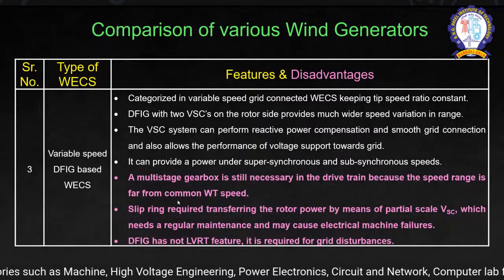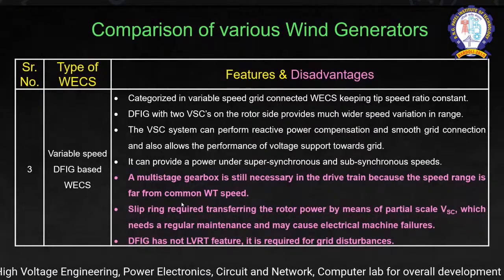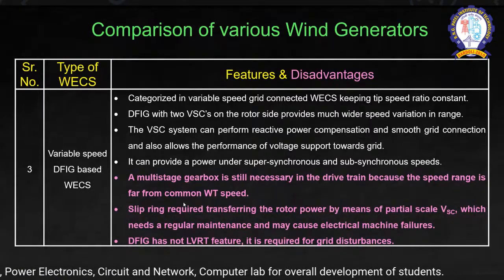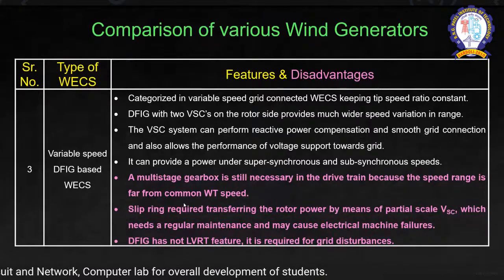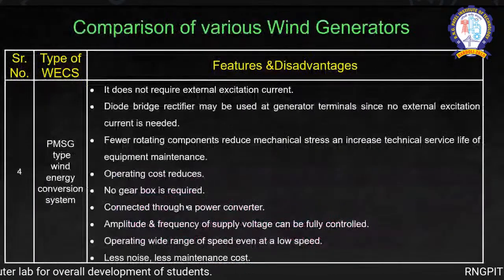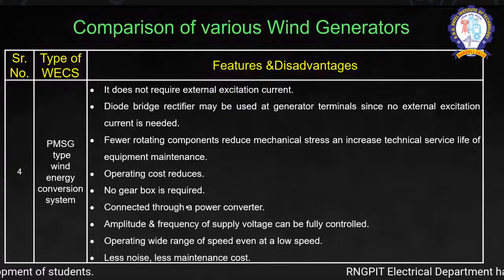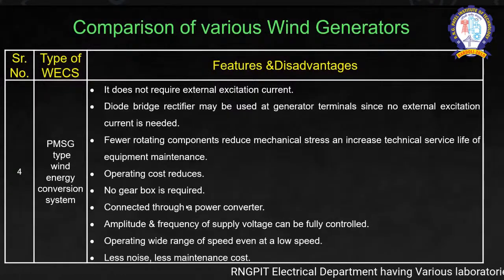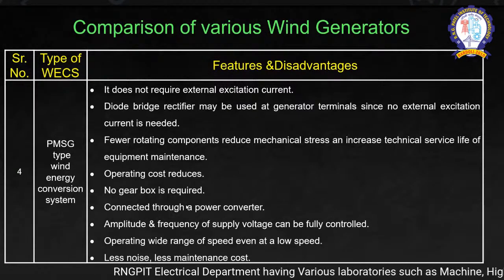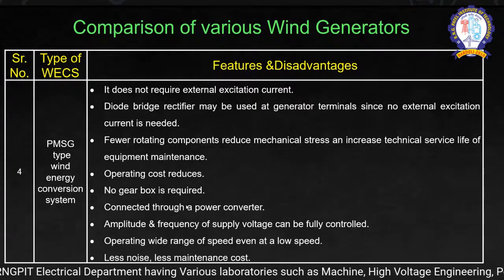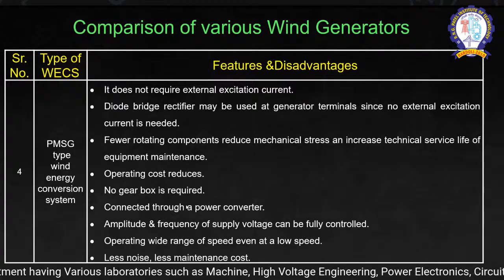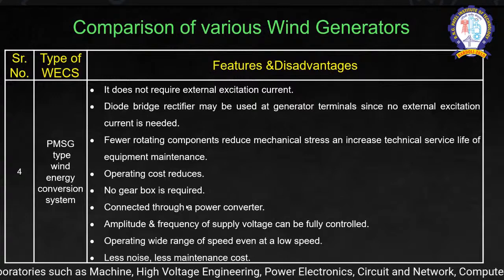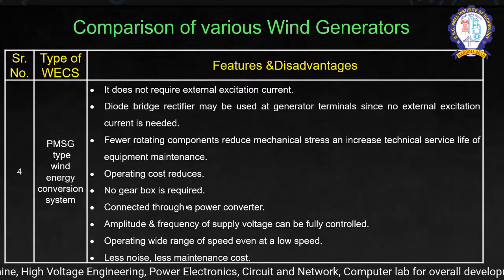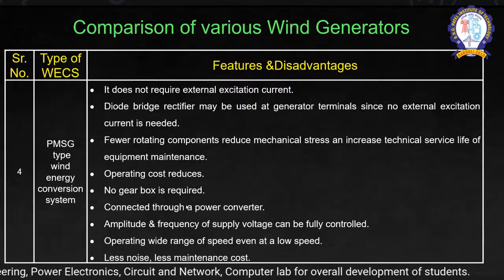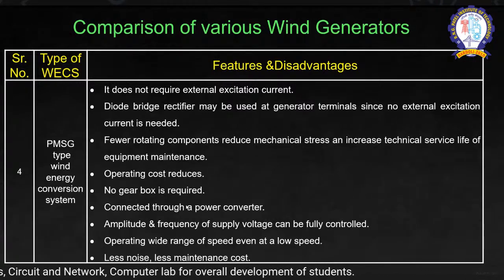In a few cases, this system is still there. Current DFIGs are LVRT capable, but they encounter certain disadvantages. Talking about the main feature of the permanent magnet synchronous machine direct drive system, as our rotor is of permanent magnet, it doesn't require any external excitation from the grid or from another DC supply.